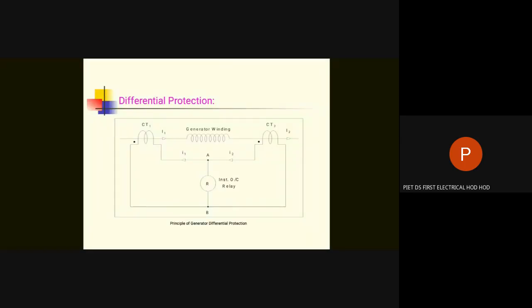Right? Double line fault, if at all it occurs, the magnitude of the double line fault will be very large. If you calculate based on the positive sequence and negative sequence impedance, then it would be of the order of some 333%. That is, from 9,000 ampere, it would rise to some 27,000 or 30,000 ampere. And this large current is dynamically damaging. Dynamically damaging means the generator would just burst within cycles. Therefore, double line fault is a very dangerous fault. It has to be taken care of very fast, very immediately, and therefore we are using the instantaneous overcurrent relay.